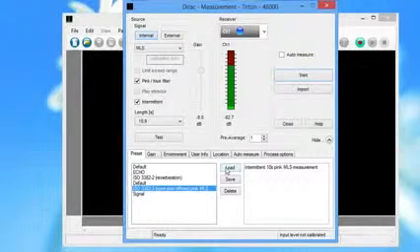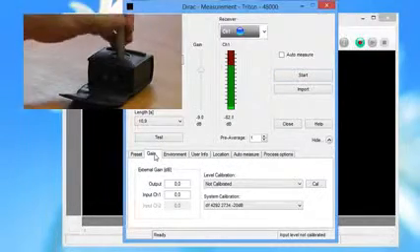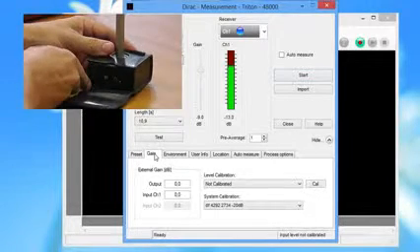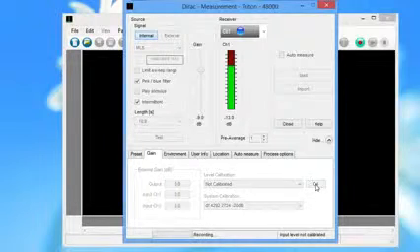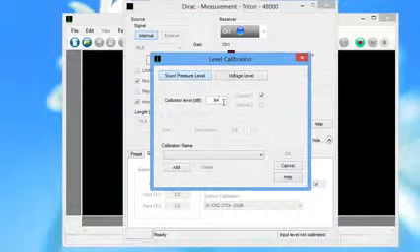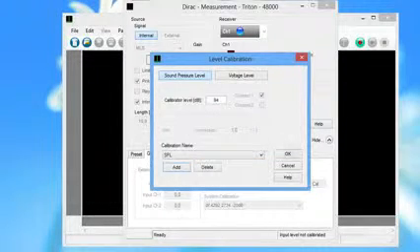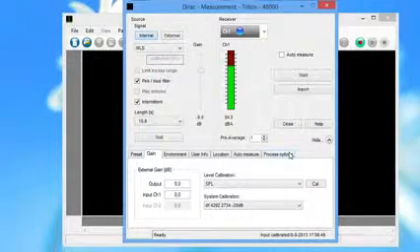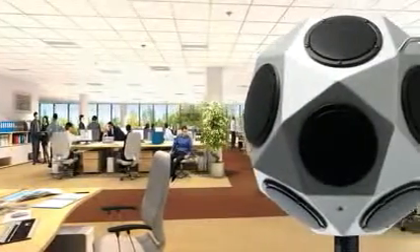First, you need to perform a level calibration. Insert the microphone into the calibrator and start the calibration on the Gain tab. Enter the level, calibrate again here and use the default name for the new level calibration. Now perform measurements at different workstations with different distances from the source.